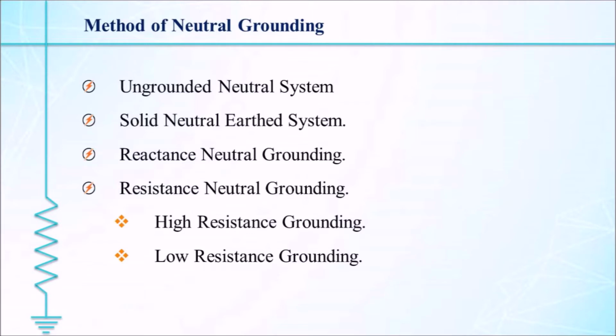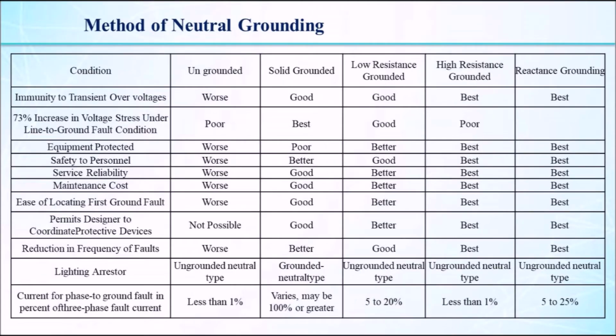An ungrounded system has a high risk of shock hazard. This drawback is overcome by the direct grounding system, but when a fault occurs, a very high amount of fault current will flow through the winding, which leads to severe damage to the winding. For this reason, and also to maintain service continuity, the NGR system is often the method of choice. We classified all the methods here from the following conditions.